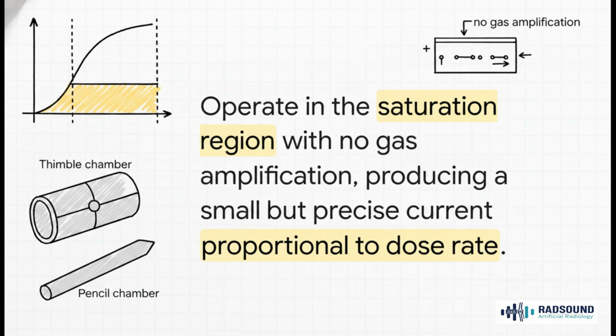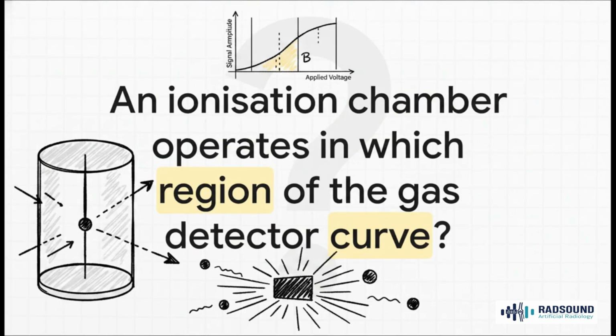So, the most important thing to remember is that ionization chambers live in that nice, stable saturation region. They don't amplify the signal at all, they just precisely measure the primary charge that was created. And because of that, they are the absolute gold standard for dosimetry and calibration. When you think about the thimble chambers used to calibrate treatment machines, or those long pencil chambers for measuring CTDI, you're thinking about precision.